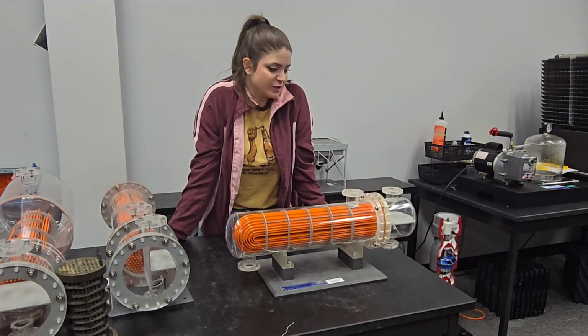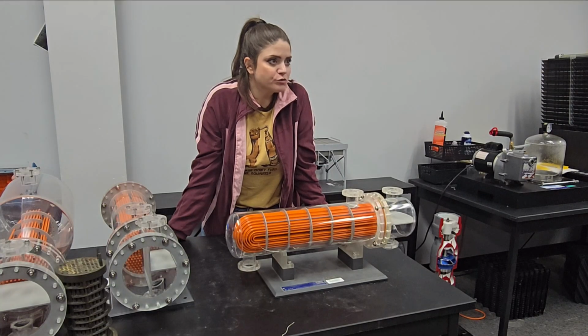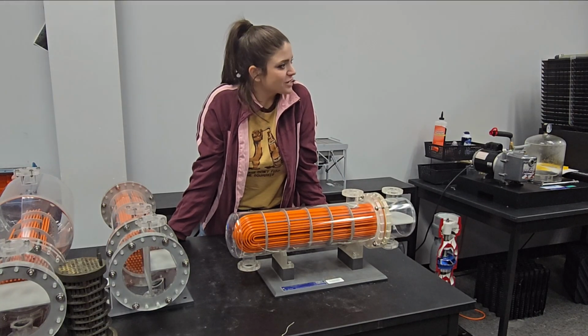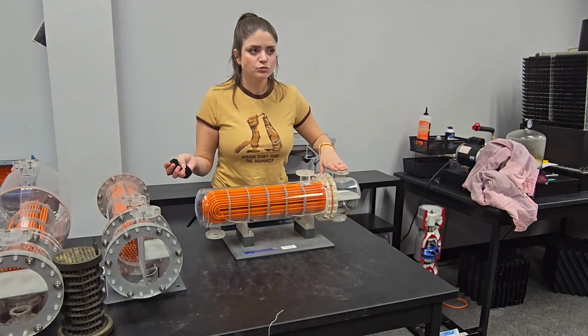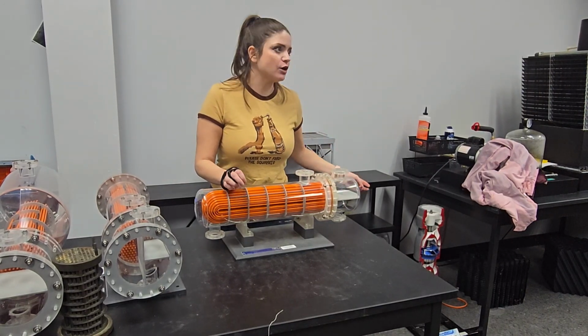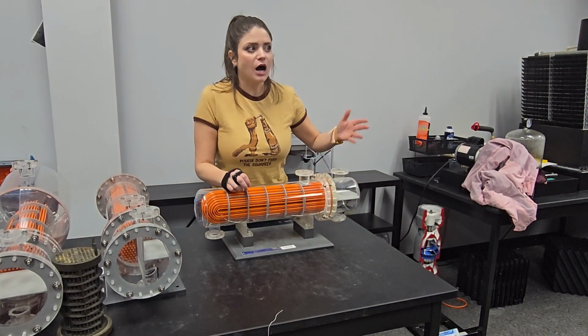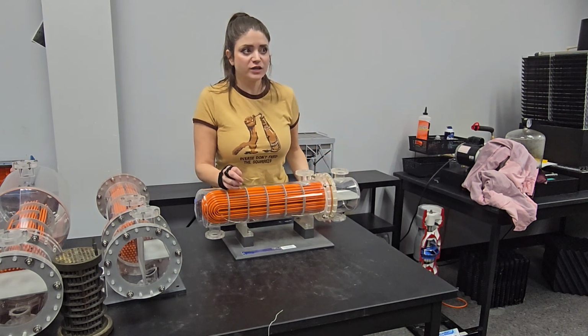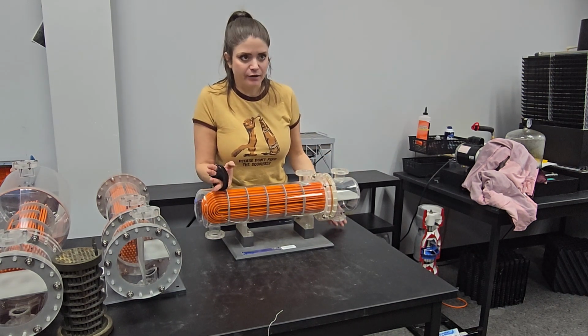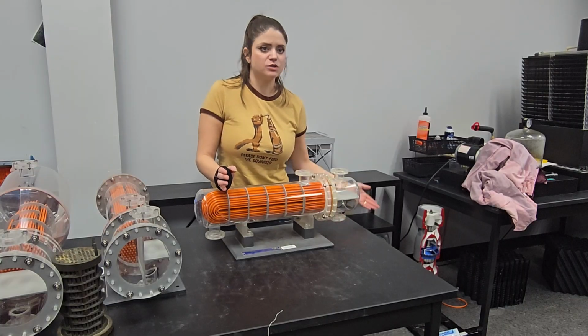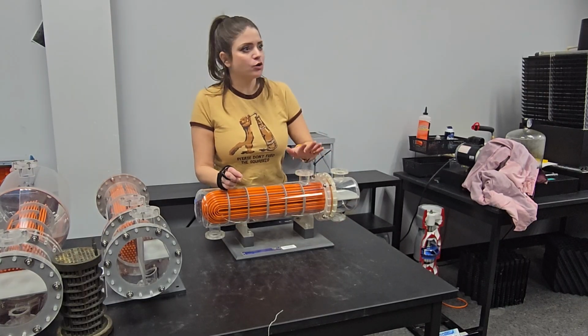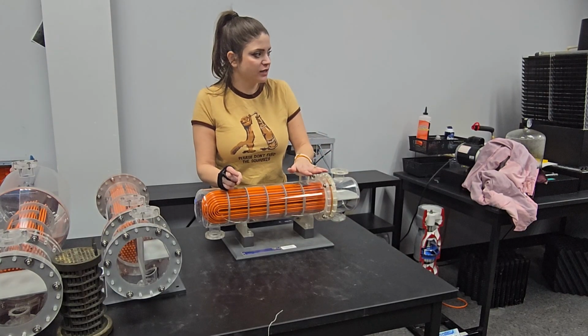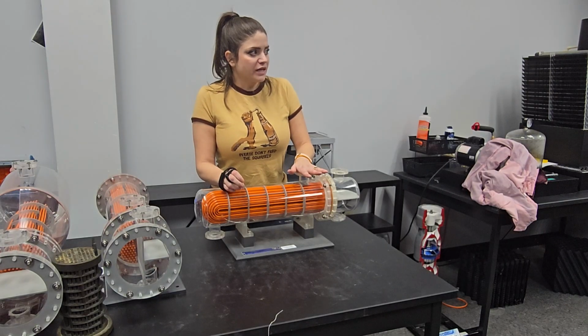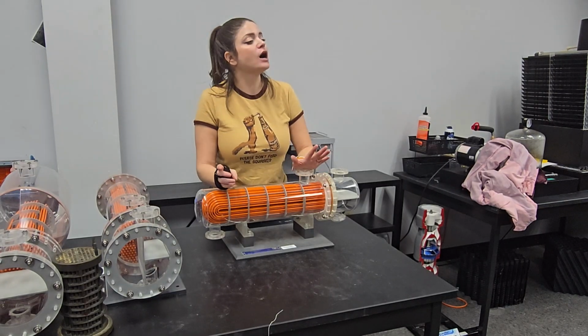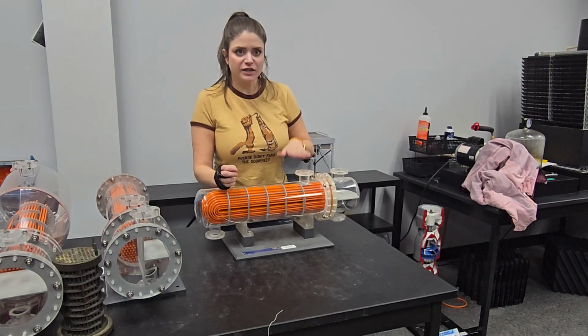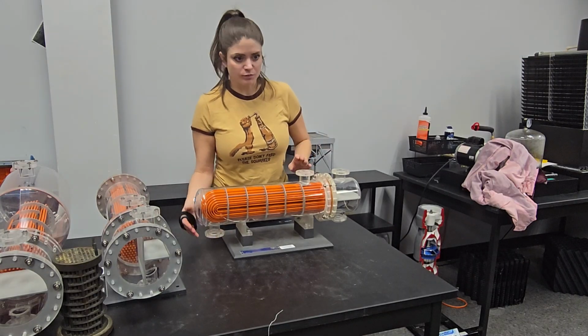Heat exchanger rule of thumb: if it's cooling water on your tube side and oil on your shell side, you heat something down. Heat it up. So if it's going in cold, we know it's coming out hot, or warm, right? So is the cooling water that's going in cold getting heated up or heated down? Heat it up. So it'd go from bottom to top. Now the oil is getting cooled by the cooling water, right? We're transferring heat. So it's getting cooled down, not cooled up, right? That's not a thing. So where's our inlet gonna be? Top, out the bottom. Okay.